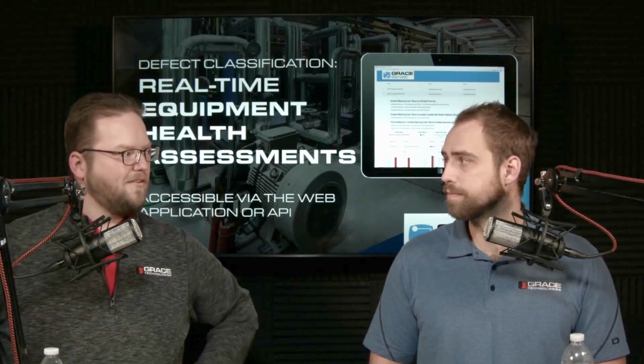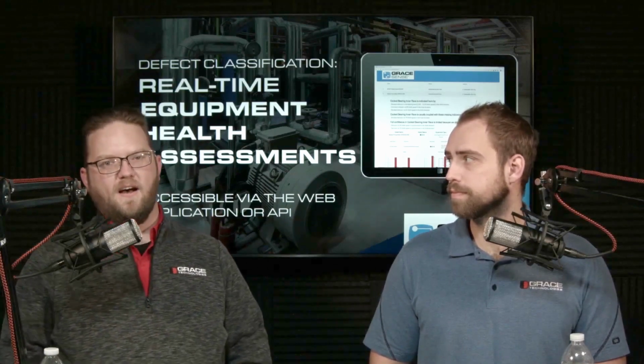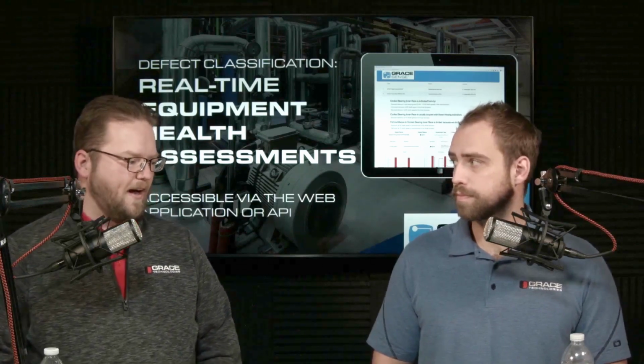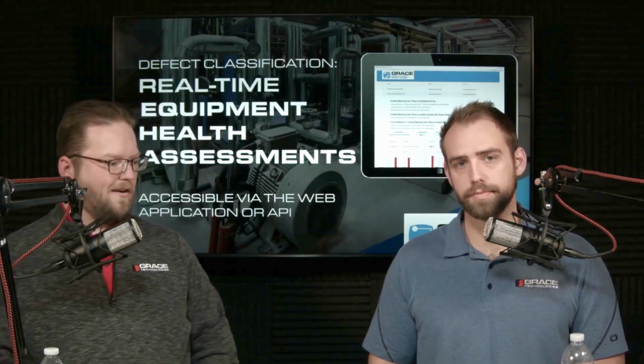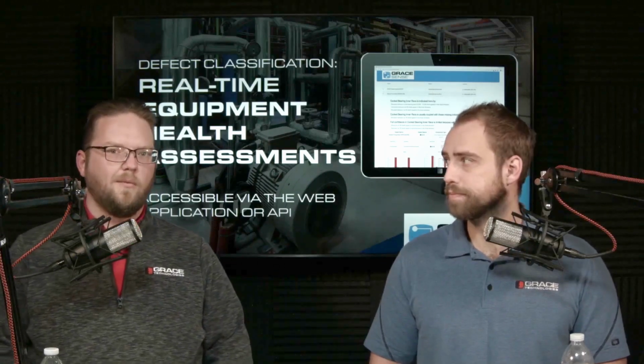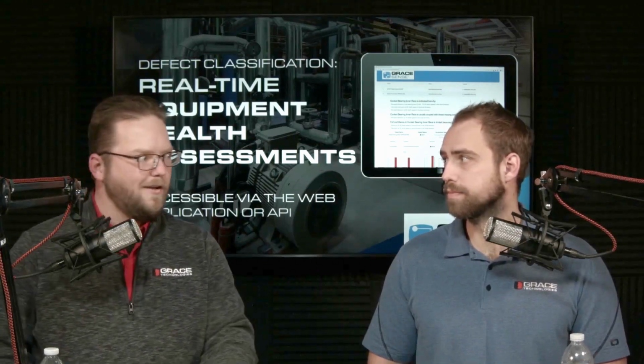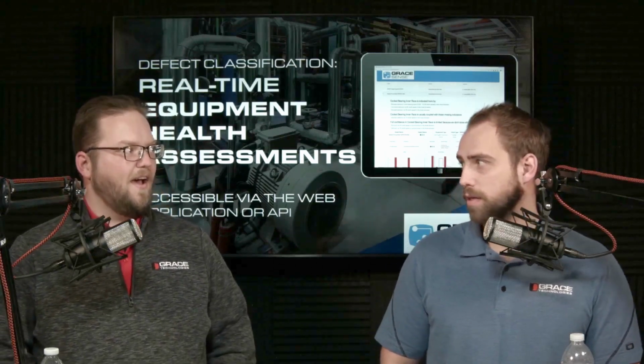In our conversations over the past few years, we found a lot of these vibration systems, like asset condition monitoring, have been installed and pretty much gone derelict inside facilities. There's equipment that's sat unaccessed for years. When we ask why they're not using that system, ours or any other, it's because they don't know what to do with the data. They got so many alarms that didn't matter, or alarms they already knew were coming, but an alarm doesn't tell you anything other than it's shaking and you could feel that walking by. Something's wrong. So they get really frustrated.